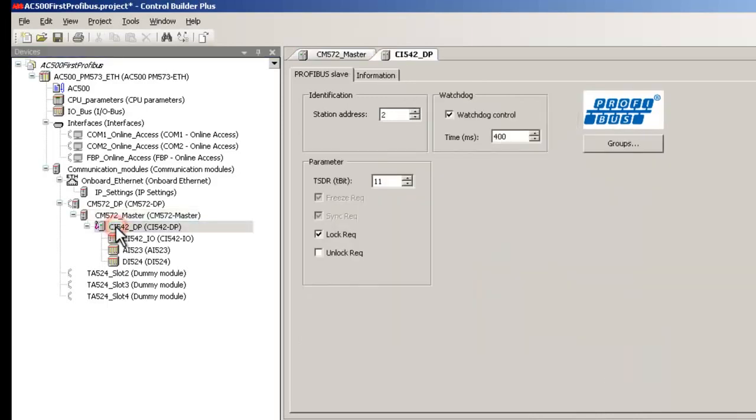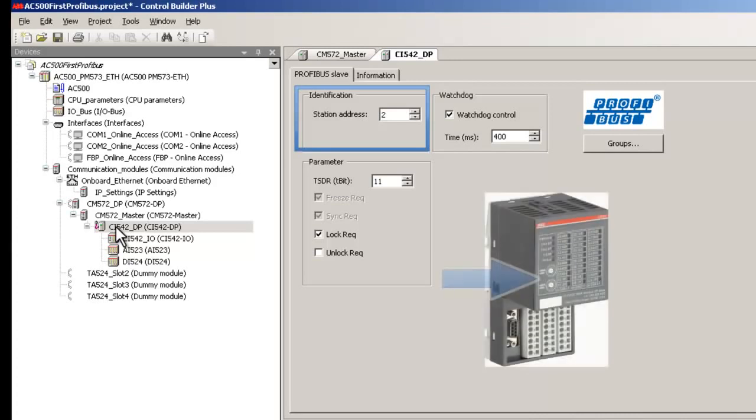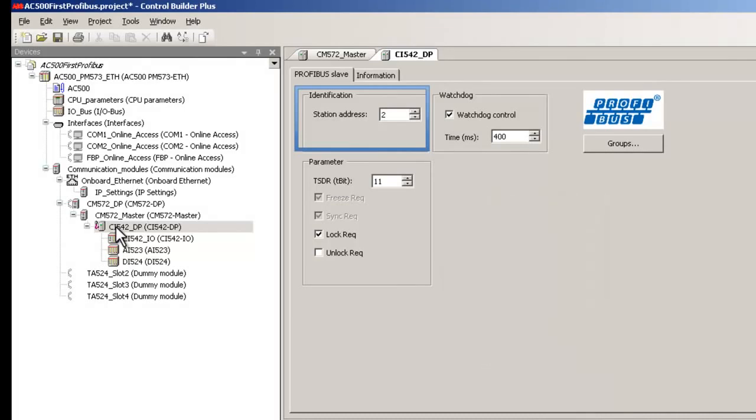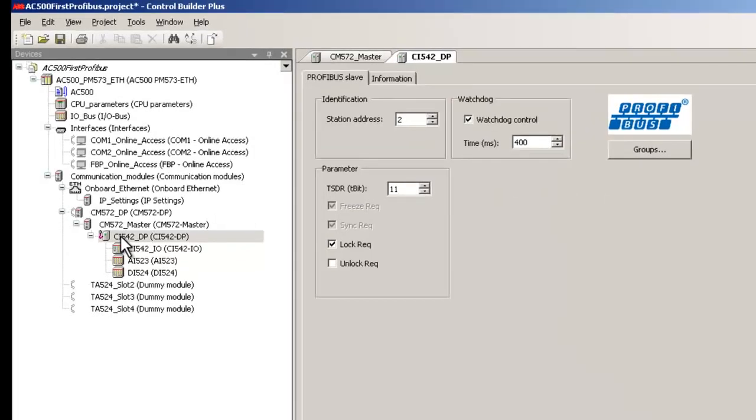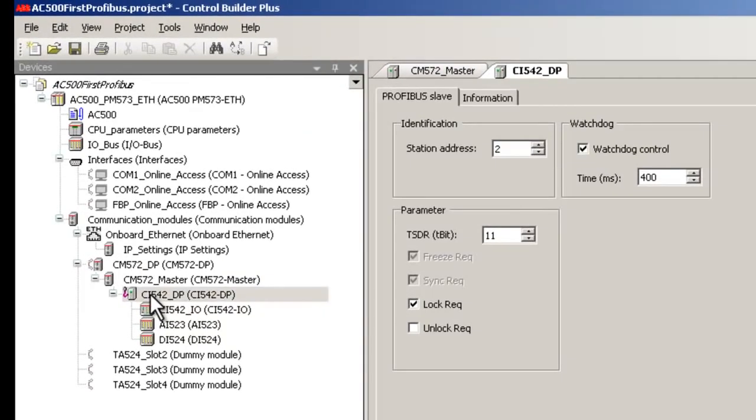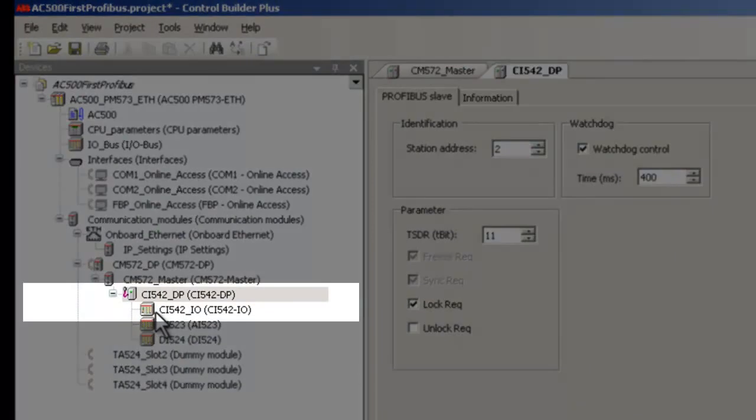Similarly, double-click on CI542DP branch to set the bus parameters for the slave. Important setting here is the PROFIBUS address, which is to be done as per the hardware settings made in the slave module. Rotary switches are available on the slave to make the address settings, and once again we leave it to default address 2.